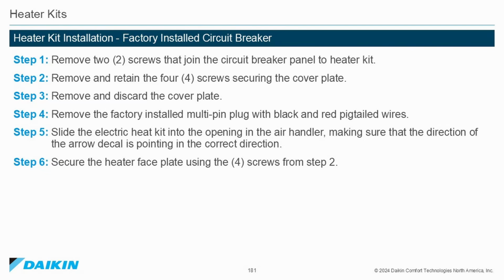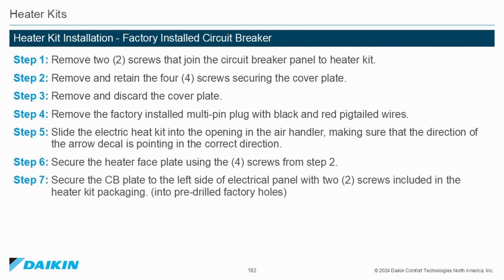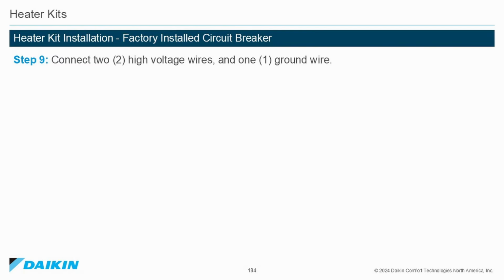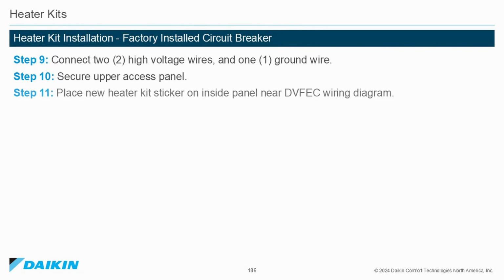Step 6. Secure the heater faceplate using the 4 screws from Step 2. Step 7. Secure the circuit breaker plate to the left side of the electrical panel with 2 screws included in the heater kit packaging into the pre-drilled factory holes. Step 8. Connect the multi-pin plug and ensure that the wire colors match. Step 9. Connect 2 high-voltage wires and 1 ground wire. Step 10. Secure the upper access panel. Step 11. Place the new heater kit sticker on the inside of the panel near the wiring diagram.